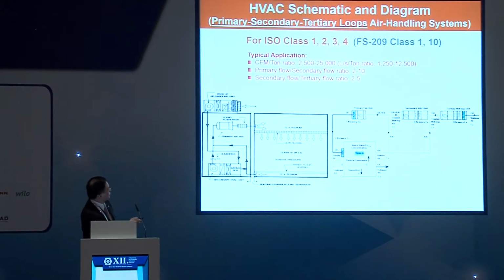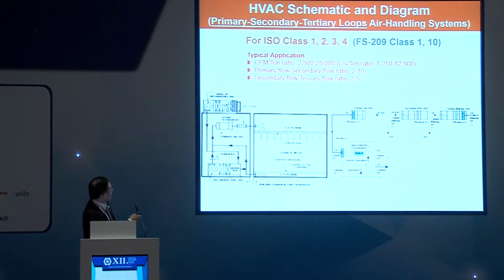So if you look at the airflow rate ratio between the tertiary and the secondary, the fan for the secondary may be 2 times or 5 times more flow. The recirculation fan may be another 10 times bigger. So in other words, the fan for the tertiary is very small, basically just for outdoor air. But the recirculation airflow rate is much, much higher. So that's another reason multiple loops can control room temperature and humidity better, and also typically utilize less energy to achieve the requirement.